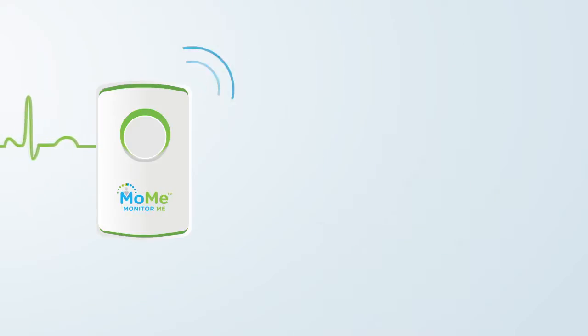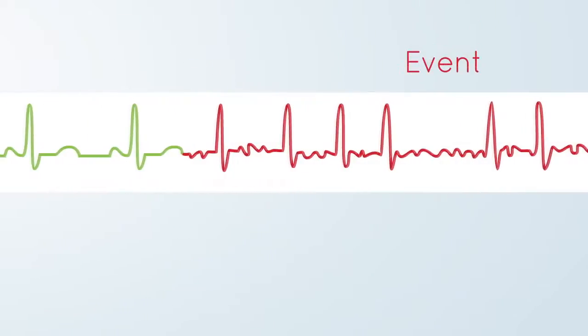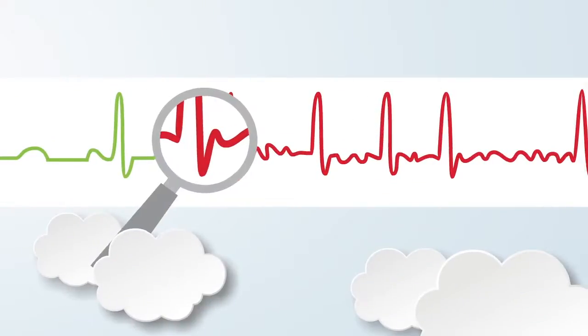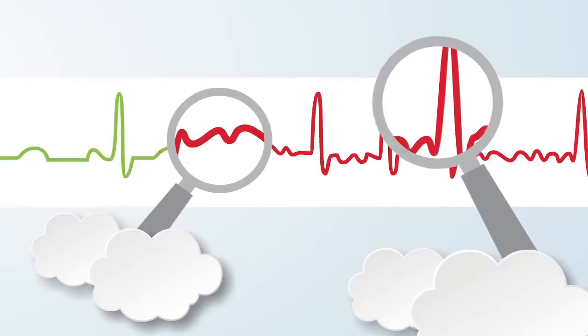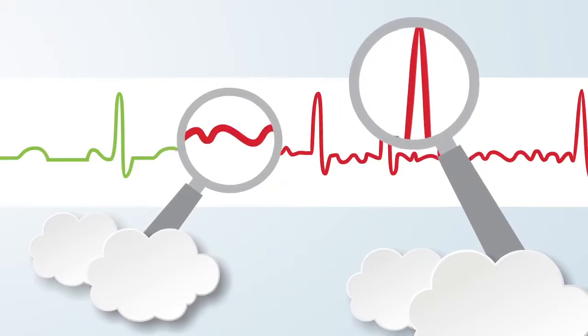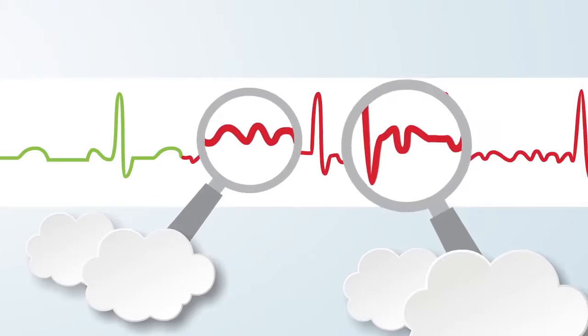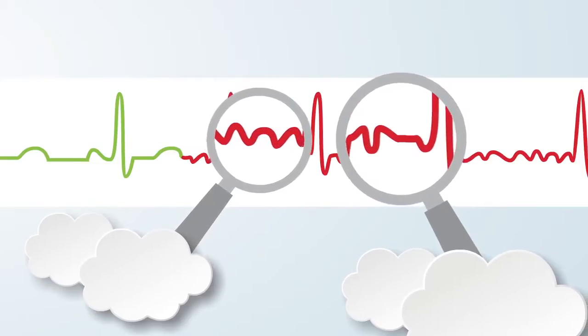All potential arrhythmias are certified with multi-pass analysis, designed to remove false positives. This second advanced analytic evaluation, using the high-definition signals stored on the device, in addition to respiration and motion data, ensures accurate arrhythmia identification.